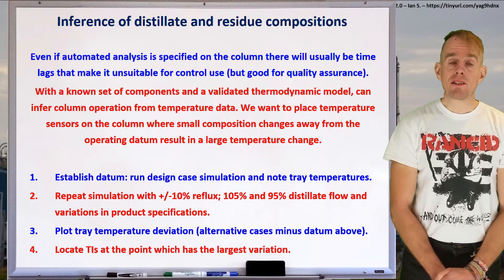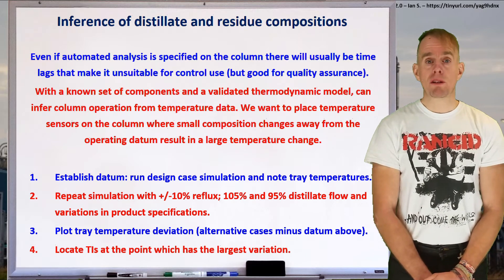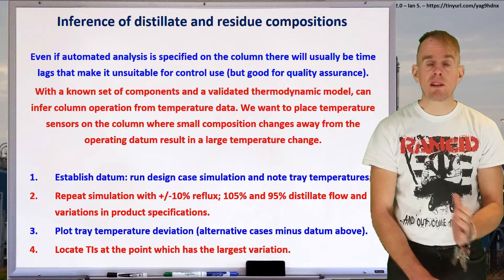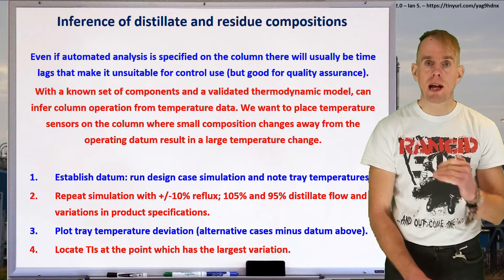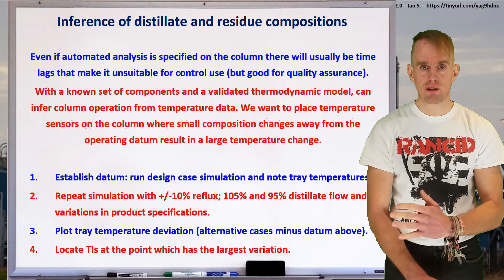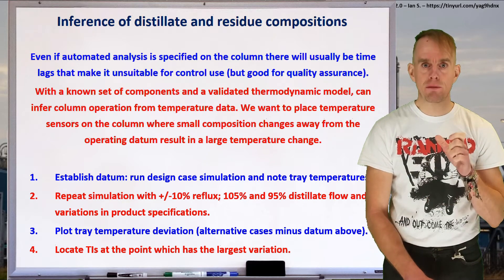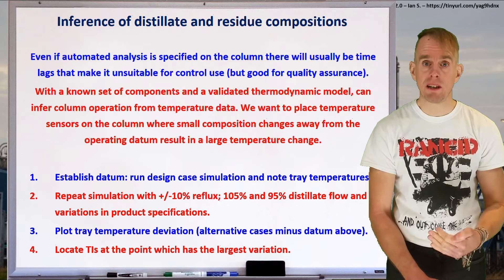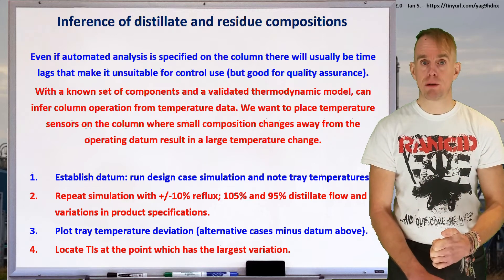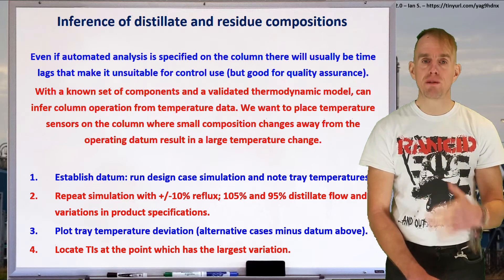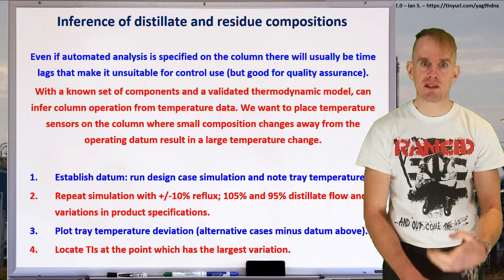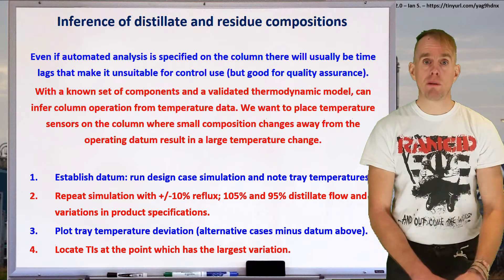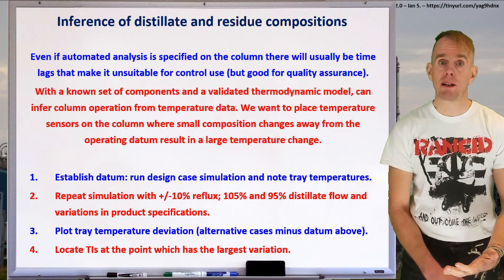We will quickly see when we plot temperature deviation that there are going to be points in the distillation column that have a broader deviation than others. It's these points where we get the largest temperature swing that we want to measure. This is why at the design stage it's a very useful thing to do, because we can design in where we're putting our thermal wells.